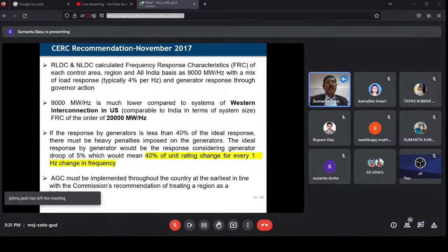As I told, our minimum frequency or nadir value is 49.5, the quasi steady state frequency is 49.8, and the area control error has to be set at 4%, not more than that. So these are the approaches towards the smart grid, because the final objectives of the smart grid, as I told, are quality power, stability of power, and integration of various energy sources.